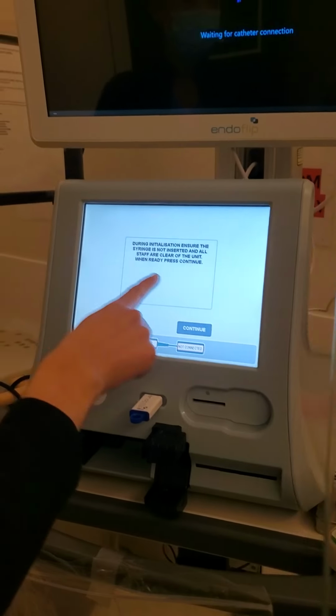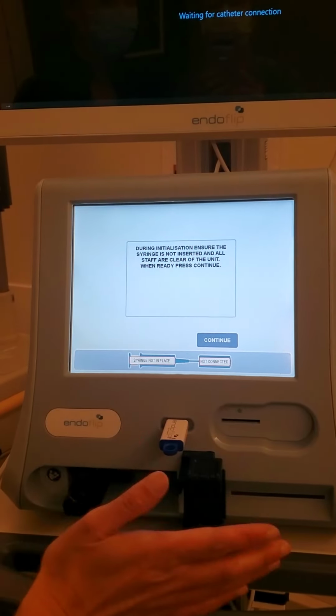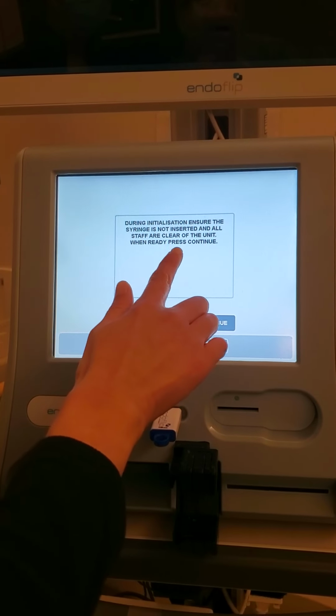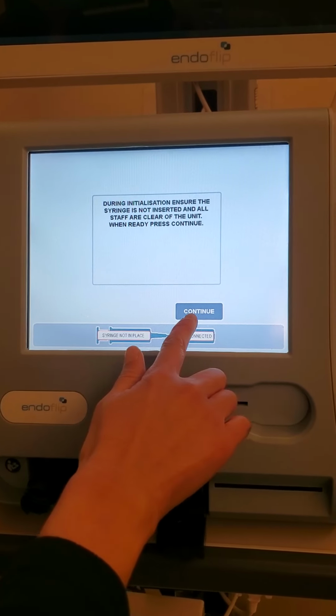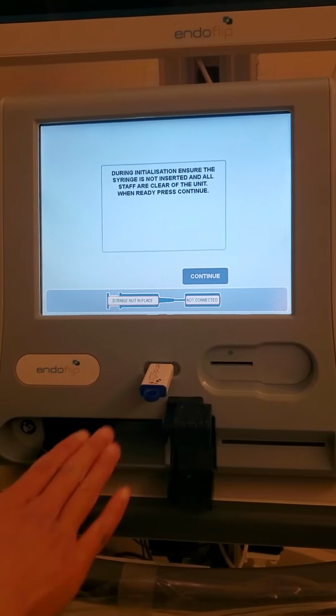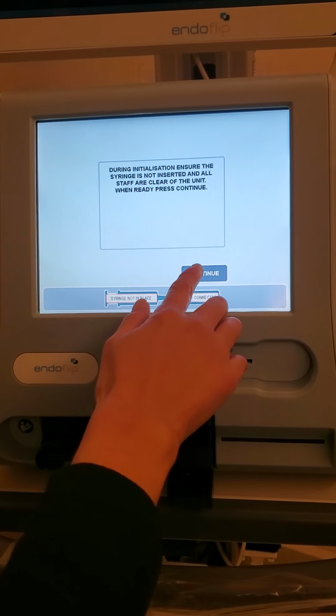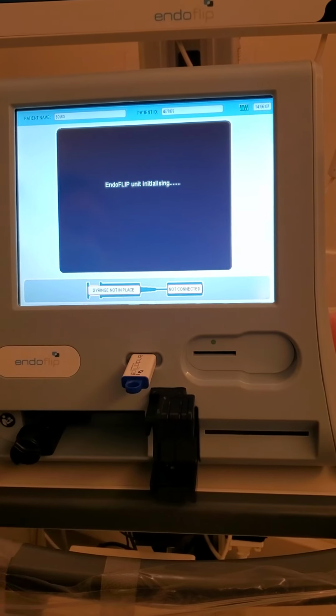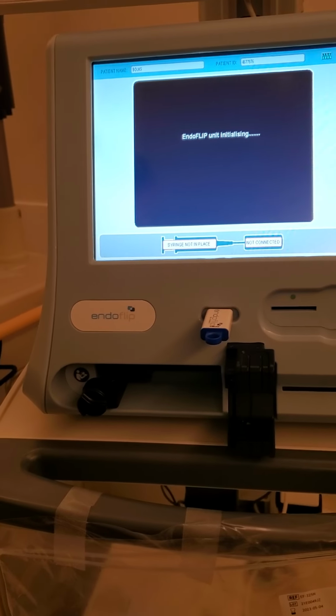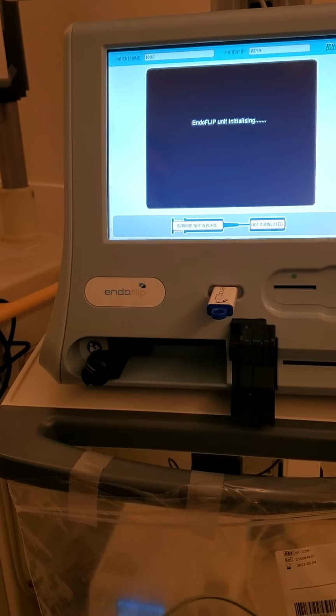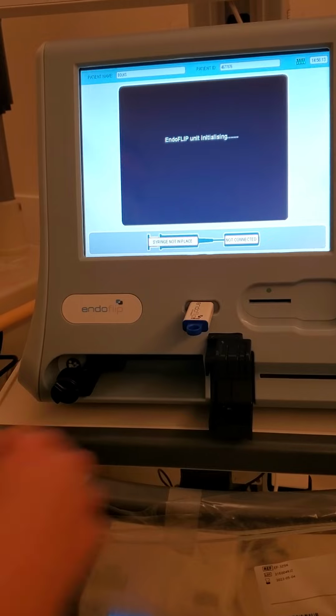And now it says, during initialization, ensure the syringe is not inserted and all staff is clear of the unit, and then press continue when ready. So that just means don't touch this pump arm right here. Press continue. The reason why is because this needs to move back and forth freely as it adjusts on its own. So we don't want to bump it or prevent it from moving back and forth.